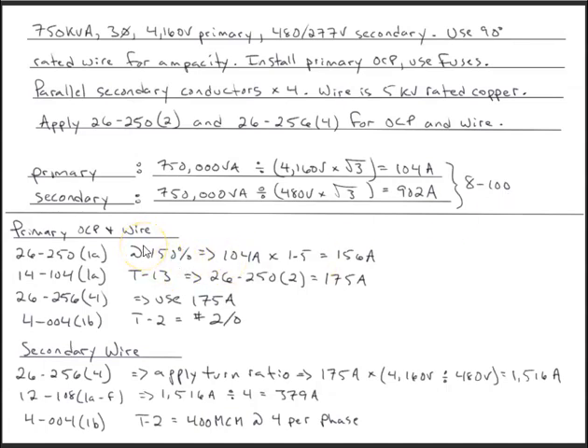So always remember that. So we're looking at the primary overcurrent protection in wire, 26250 subrule 1A. We're going to take it at 150%. So we're going to take 104 amps times 1.5 gives us 156 amps. Now notice here, we're dealing with the overcurrent. So when we're dealing with overcurrents, we're typically dealing with the language of maximum. However, 26250 subrule 2 allows us to increase the size. So we'll go to 175.